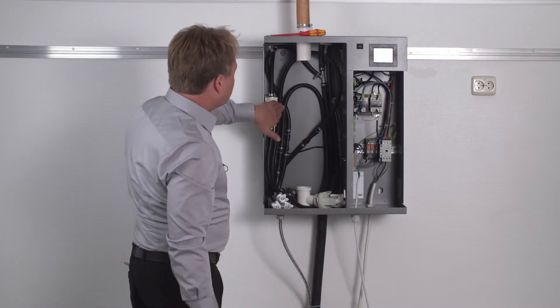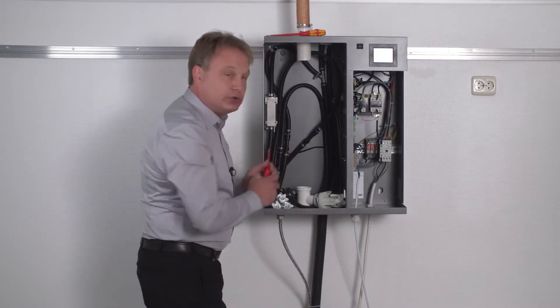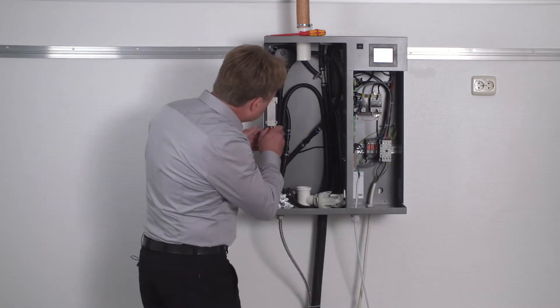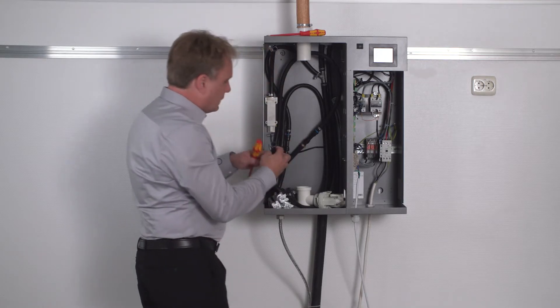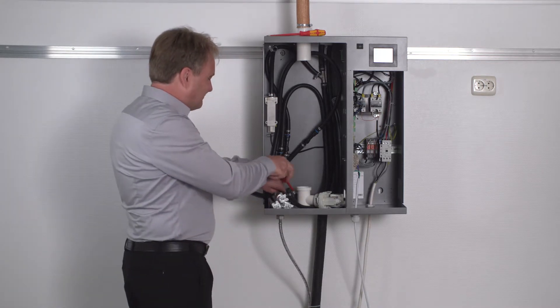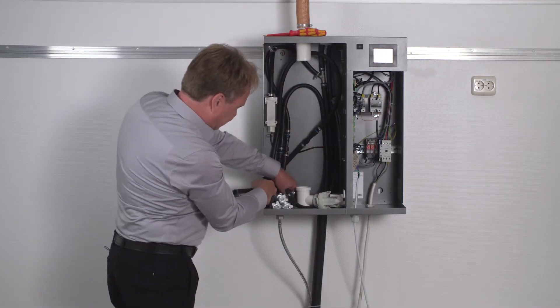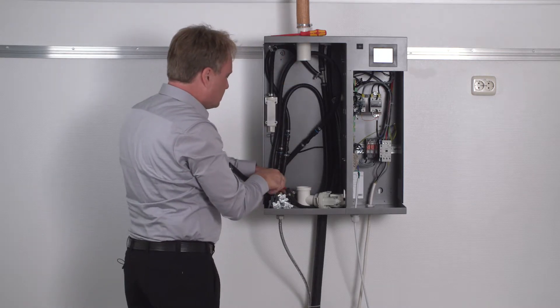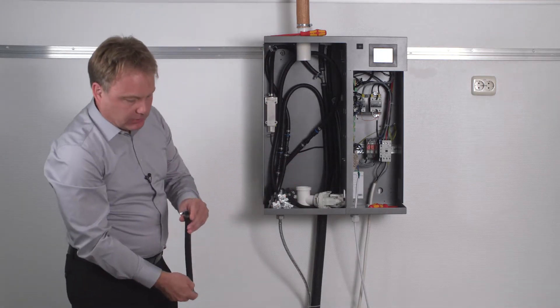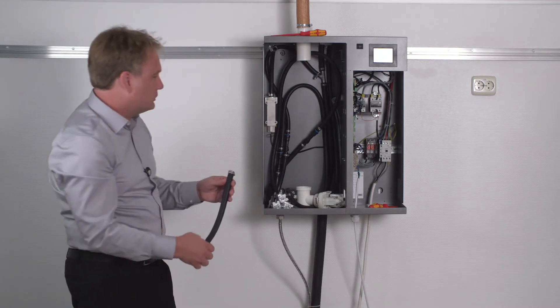Here is the water level control device. It is maintenance-free. To check if it still works, I simply disconnect this hose after I have loosened the hose clip. And I also loosen the hose directly at the cylinder base. I'll take a look at this hose too, whether there are mineral deposits in it, which I could possibly just knead out.